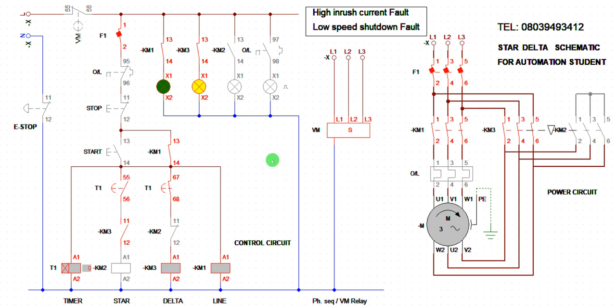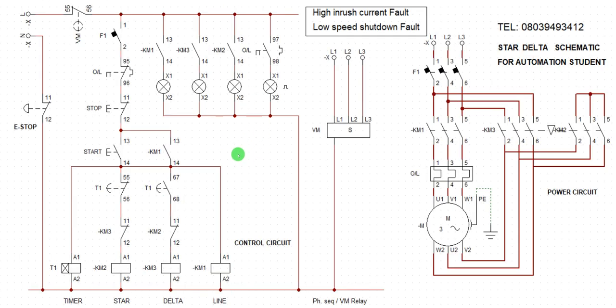Now let us point out the error in this design. When star is on with the line contactor, the motor runs on low speed. When line and delta are on, the motor runs on high speed. Now, the first fault: high in-rush current fault. This means the star contactor is not working — only the delta contactor and main contactor are working. When the system runs on delta only without star, that is when this fault arises.